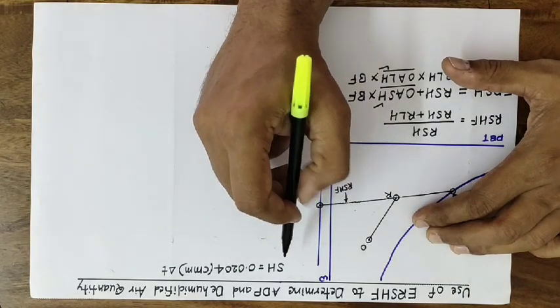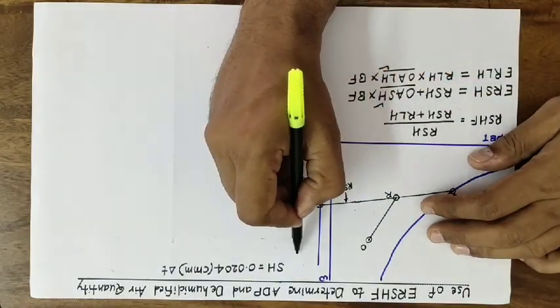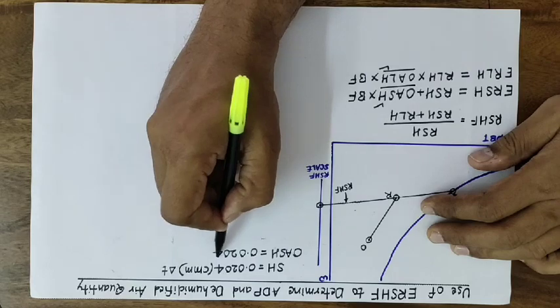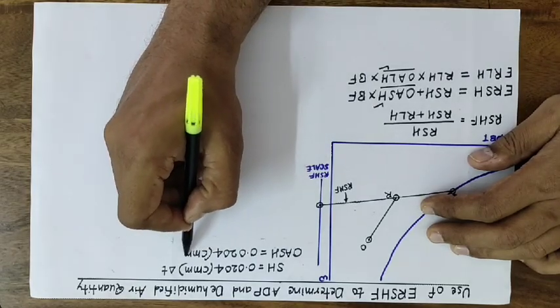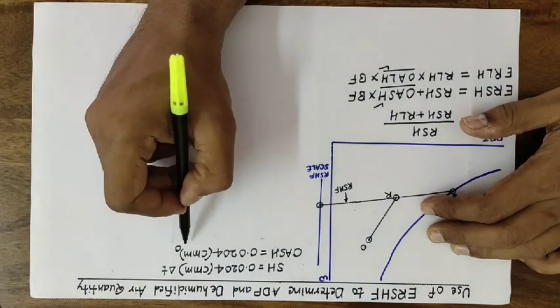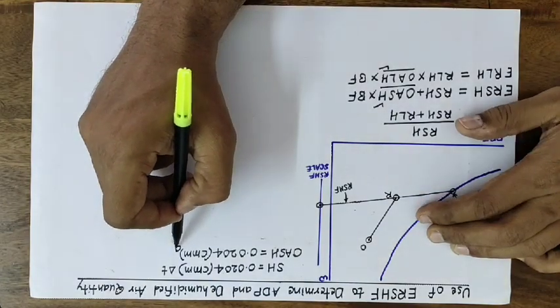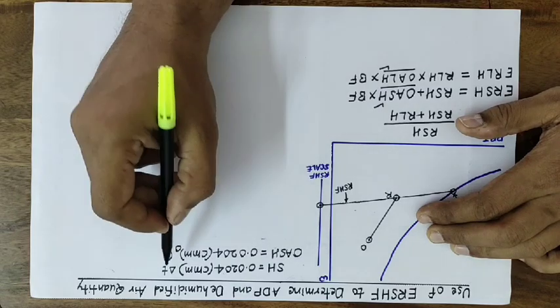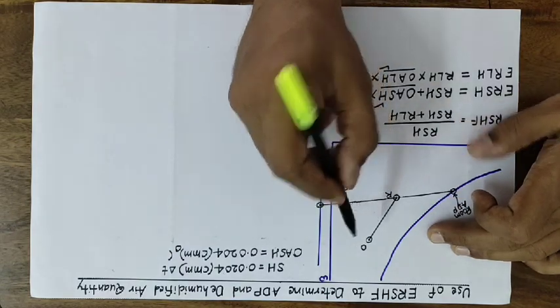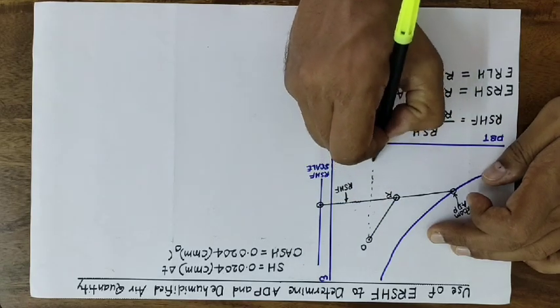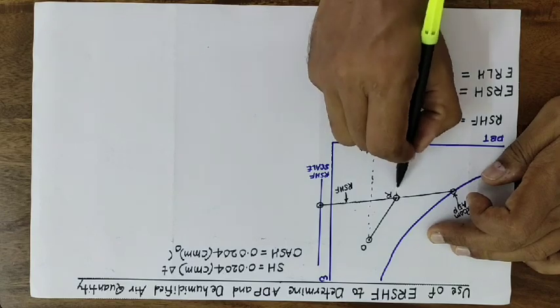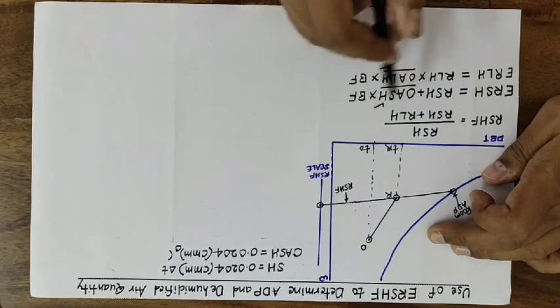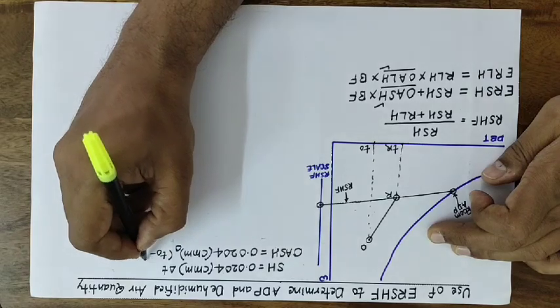The same formula can be used to calculate outside air sensible heat: OASH = 0.0204 × CMM_O × (T_O − T_R), where the suffix O denotes outside air. The outside air volume flow rate must be known. The temperature difference used is T_O minus T_R because the outside air eventually comes to room condition after rejecting heat to the room.